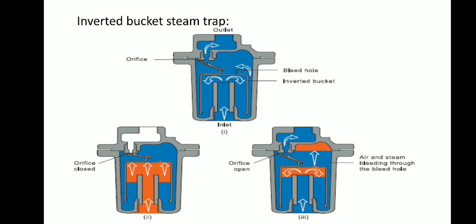The main advantages of the inverted bucket steam traps are: the inverted bucket steam trap can be made to withstand high pressures. Like a float thermostatic steam trap, it has good tolerance to water hammer conditions. It can be used on superheated steam lines with the addition of a check valve on the inlet. The failure mode is usually open, so it's safer on those applications that require this feature, for example, turbine drains. The limitation is that the small size of the hole in the top of the bucket means that this type of trap can only discharge air very slowly. The hole cannot be enlarged as steam would pass through too quickly during normal operation.